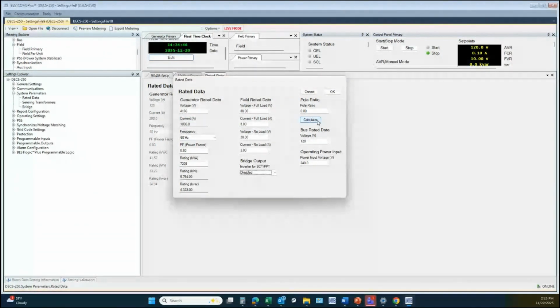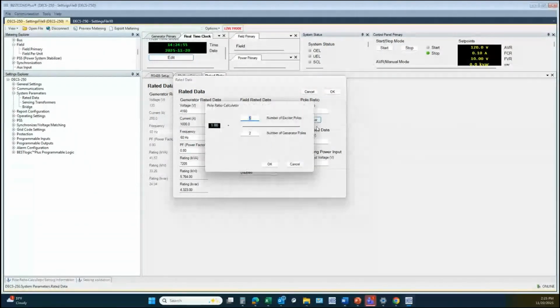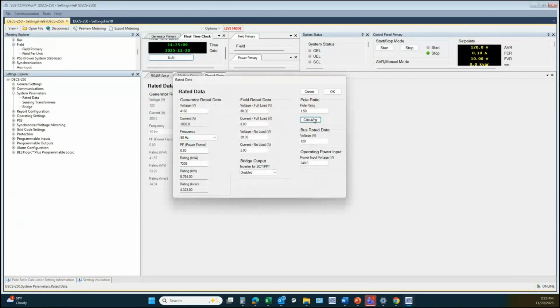If you are using the DECS 250 or 250N on a brushless excited machine, then you can set up the pole ratio, and there's a pole ratio calculator to determine the ratio, number of poles of your exciter versus the number of poles of your generator, and then it will give you a pole ratio. This number will be used if you plan to use the exciter diode monitor protection option.